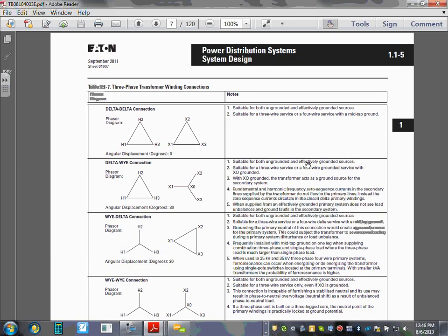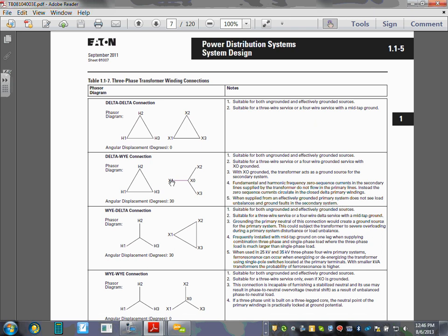Here you go. So here's when we have transformers, since they are the source of your power, you have multiple ways of doing business. I thought the most common one, of course, is the delta Y. All of us are engaged in a delta Y grounded X0 system, that's the most common one. That's where you bring the 480 from one side, and from the other side you take a 208/120 transformer for your receptacles or equipment that run at 208.